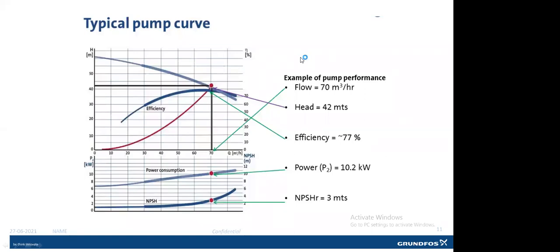So there are standard formulas available, which we can share later. For that, we need to consider the pipeline size, pipeline length, number of bends, number of valves, and pipe roughness factor. Based on that, we can calculate the frictional losses for that flow. Also, we need to take into account at which flow we are calculating the frictional losses, because there is a relation. The more the flow, the more the frictional losses. The lesser the flow, the lesser the frictional losses. If we are calculating for a fixed flow, we can use that. But if we are calculating for a variable flow, we need to consider the maximum flow required through that pipeline.